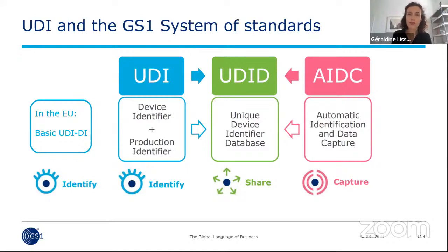And last but not least, you need to report data elements in the UDI database, which is called EUDAMED for Europe. And these 3 components, if you draw the parallel with the way we describe the GS1 system, fit perfectly into the GS1 system with these identifiers. So identify your product uniquely and globally across the world, capture that information in a machine readable format, and then also exchange that information, in that case, with the regulator, but also with your supply chain partners. So identify, capture, share is really exactly the same idea behind the GS1 system and the UDI system.